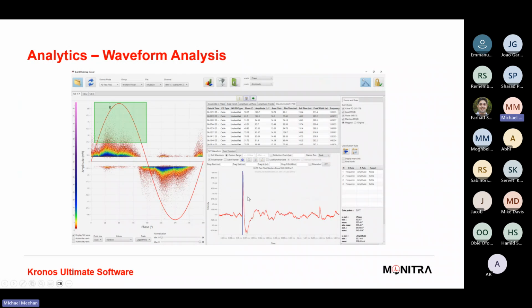So here, you'll see, this would be a typical PD pulse. And you'll see this box here, that is that pulse. And obviously there's millions of these pulses throughout this plot. Now, if you want to analyze each individual pulse, is it a pulse, is it noise, is it not noise, is it worth us taking into consideration as a potential issue? This is key because this forms part of the mapping that you're going to use to then determine is there an end winding issue or not.